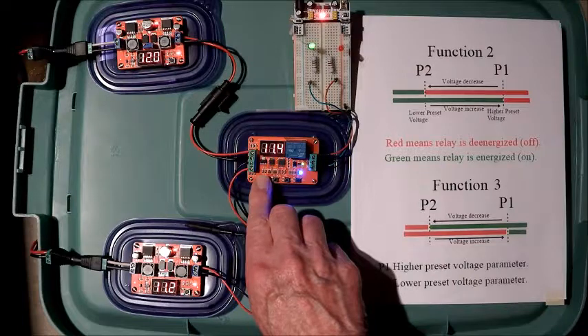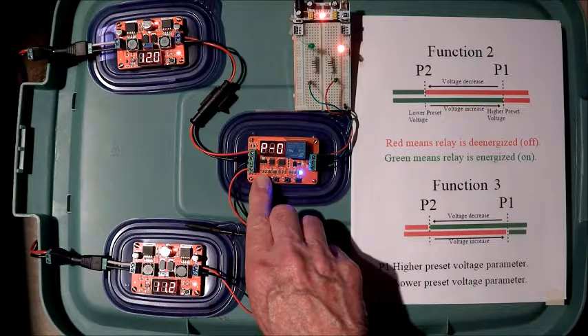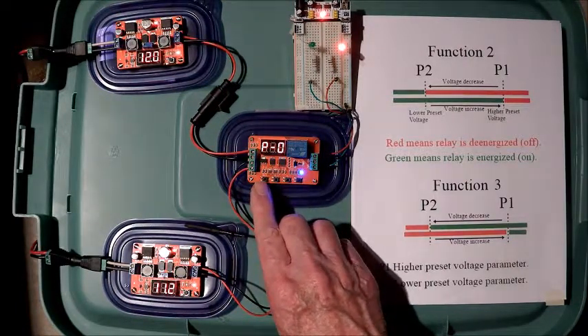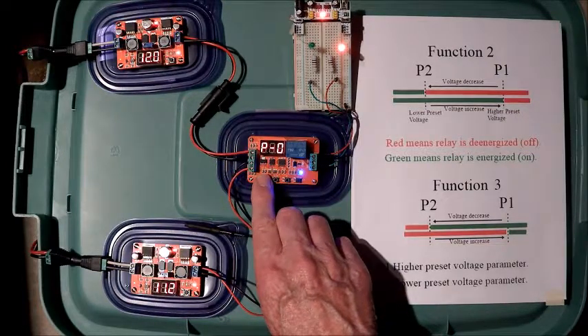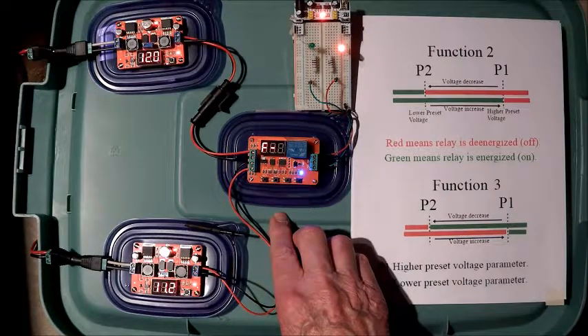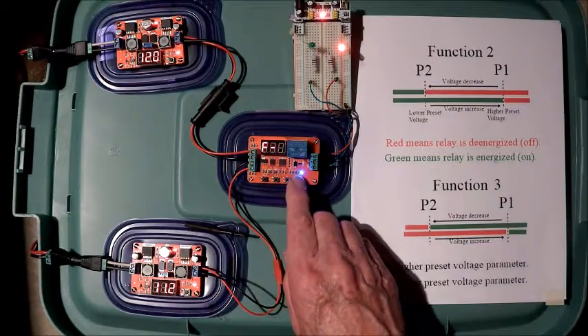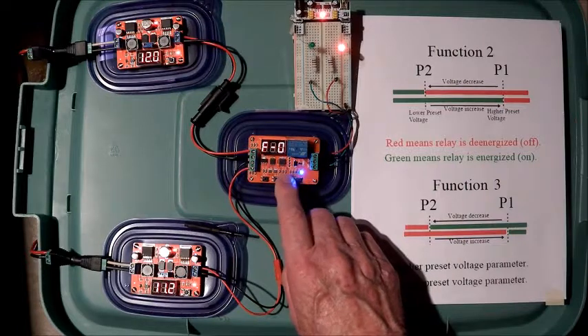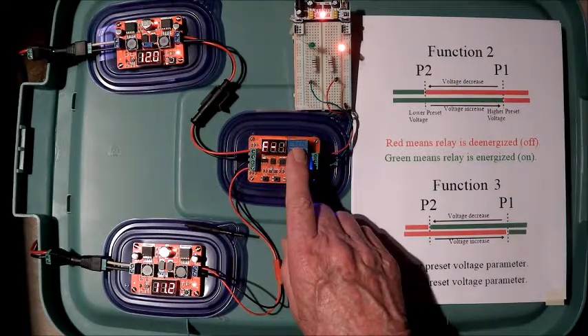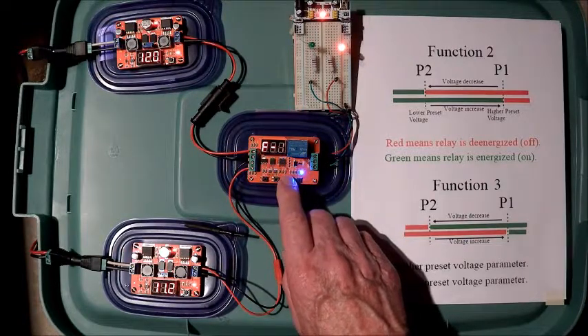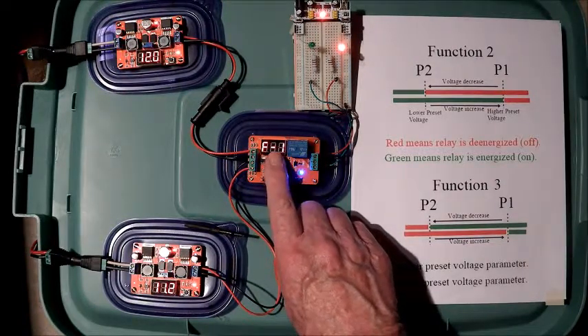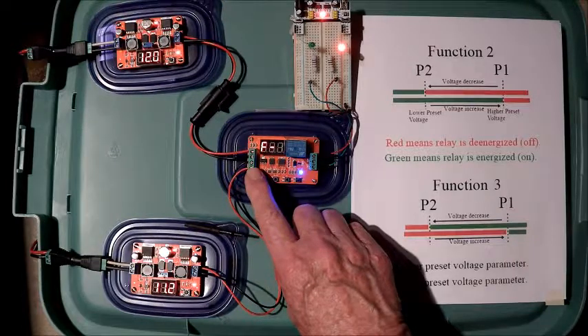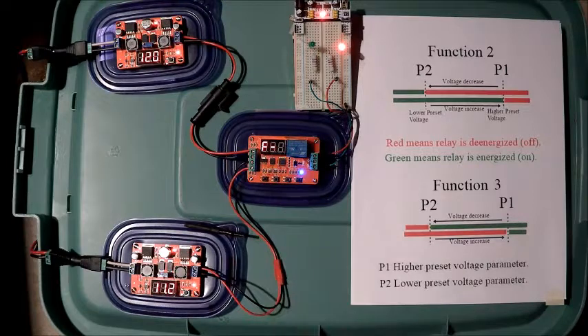Holding the set button down for over a second will take you out of the operational mode into the parameter set mode. To see what function I have selected, I will hit the set button again, and it tells me I'm at function 5. There are function 5, 4, 3, 2, 1, and 0. 0 and 1 have no effect on the relay. In 0 and 1, all you do is have the display show the value of the voltage for the measuring input. So, we will start with function 2.